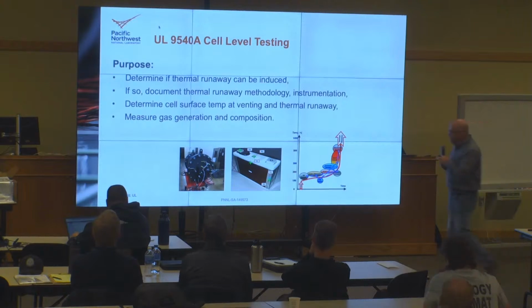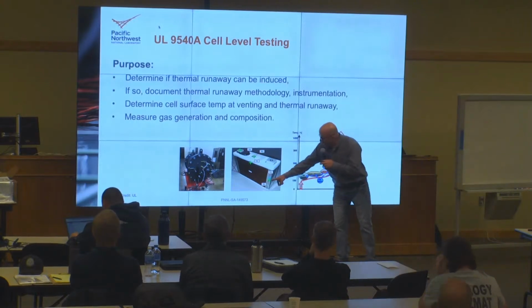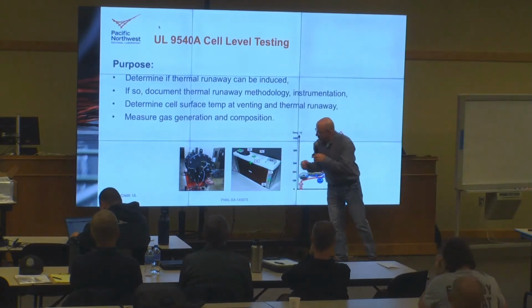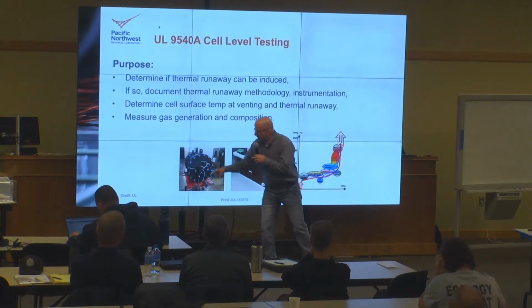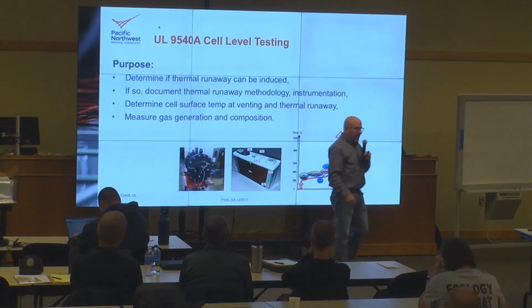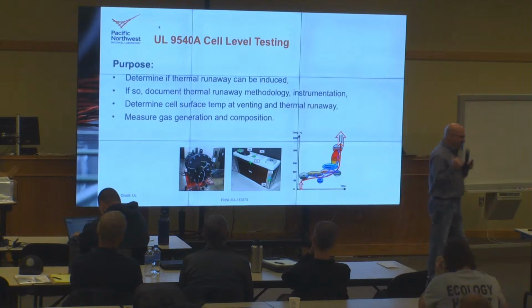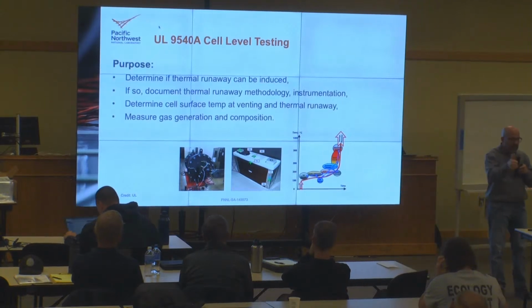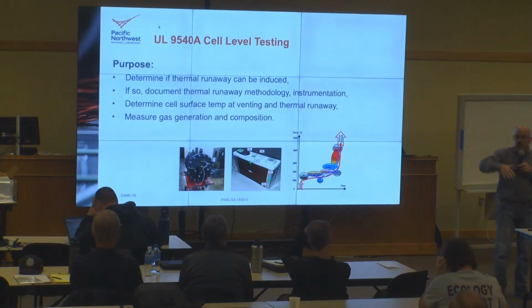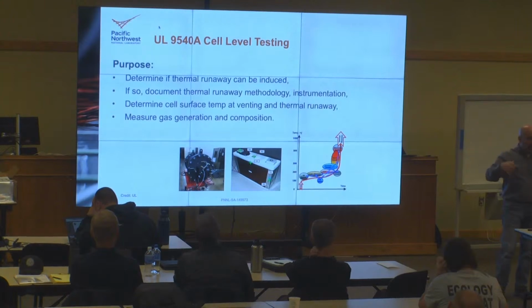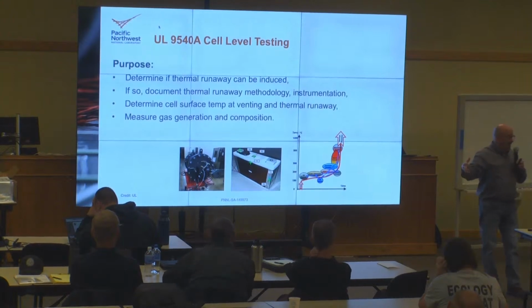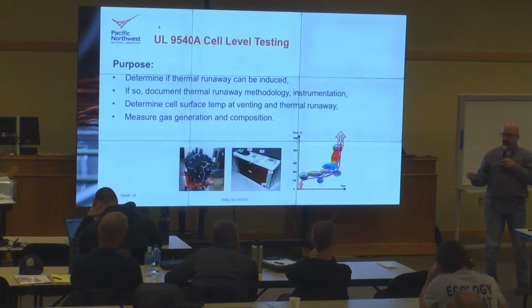Here is a prismatic cell, and what we're seeing are thermocouples at different locations, then they put it into this inert chamber. In that test they're seeing what temperature it vents at, what temperature it goes into thermal runaway, and then what gases come out of it, how fast they come out, what's the total volume of gas, and what's the lower flammability limit of that mixture of gases. So then here's that module level test.